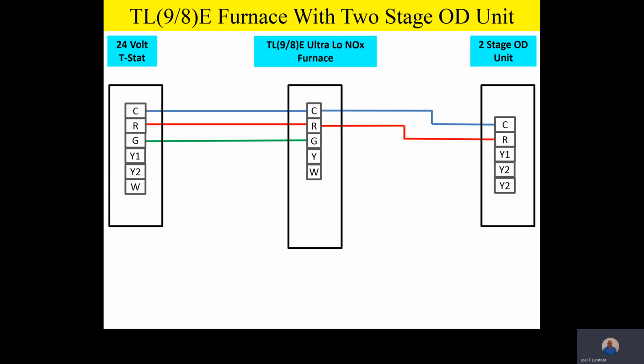So the first thing we'd like to point out, just like any other thermostat, is common, C, from the thermostat to the indoor unit and then to the outdoor unit. That's typically a blue wire, and it just goes from one to the other outside. R terminal, which is 24-volt hot, goes from the thermostat to the indoor unit to the outdoor unit. And again, most contractors use just a red wire to remind them that's their 24-volt hot.